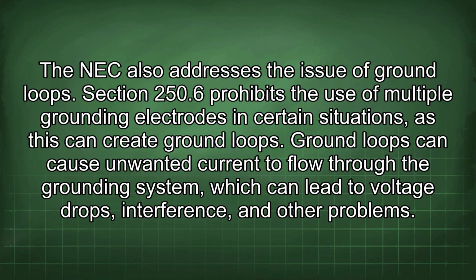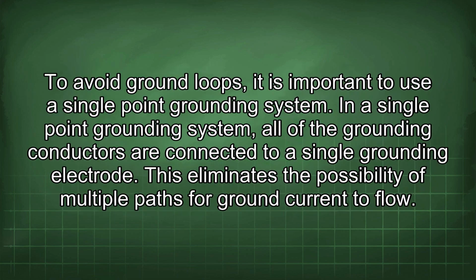The NEC also addresses the issue of ground loops. Section 250.6 prohibits the use of multiple grounding electrodes in certain situations, as this can create ground loops. Ground loops can cause unwanted current to flow through the grounding system, which can lead to voltage drops, interference, and other problems. To avoid ground loops, it is important to use a single-point grounding system. In a single-point grounding system, all of the grounding conductors are connected to a single grounding electrode. This eliminates the possibility of multiple paths for ground current to flow.